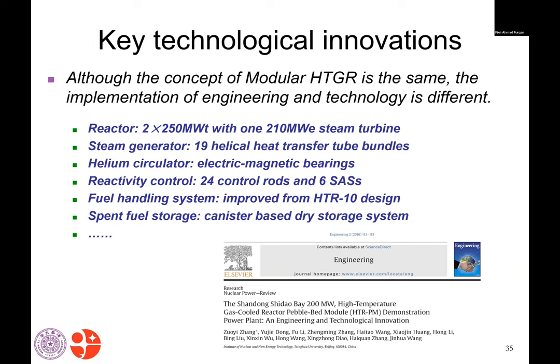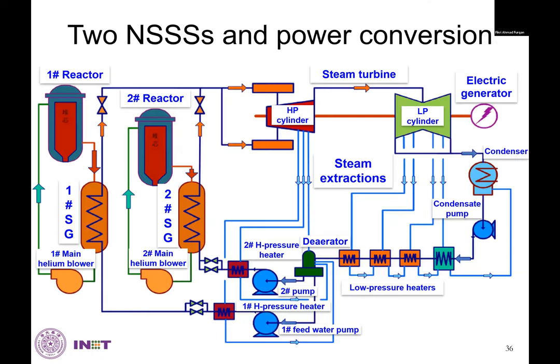All these things are new and have never been achieved in history. In this system, we have two reactors and two steam generators. These two can be run independently or combined together. The steam supplied from both reactors can run into one steam pipeline to generate electricity through the steam turbine. But we can also run only one of them while the other is in maintenance, relying on an almost independent feed water system.